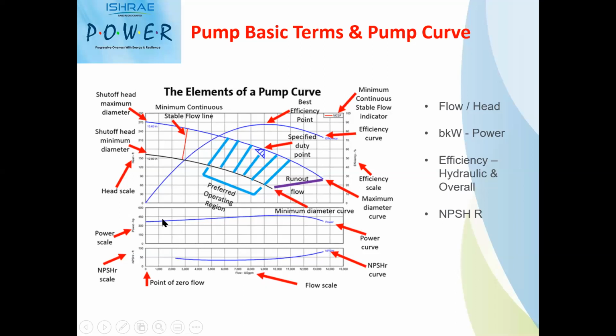So flow decides the increase in power. And then there is something called NPSH, which I will take you through in my next slides. The NPSH curve is also plotted with respect to your flow rate. Each and every pump will have a net positive suction head required by the pump. Based on that value, during the development stage of the pumps, pumps are type tested and this NPSH curve is drawn.